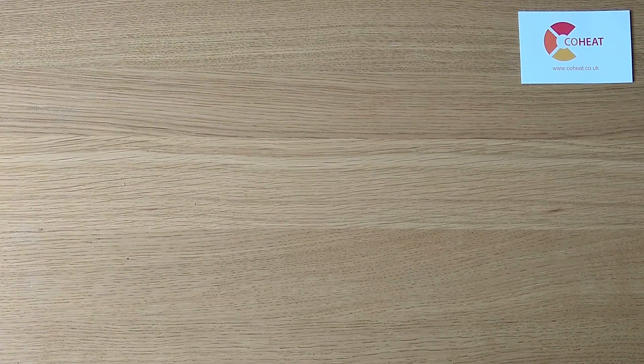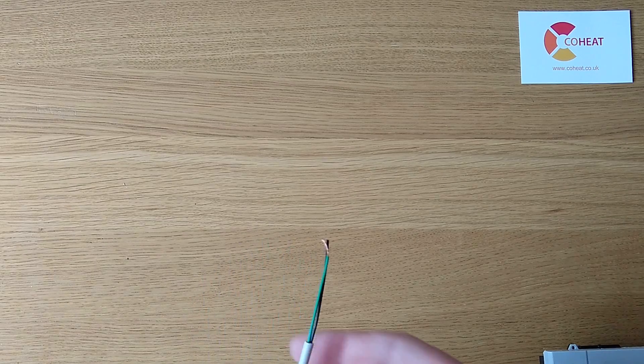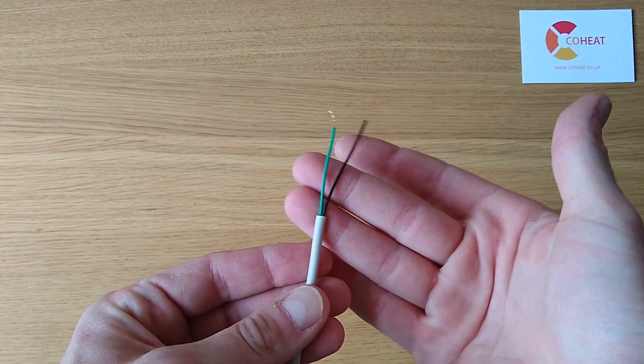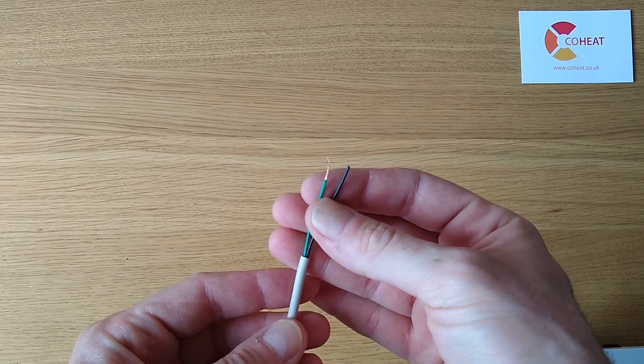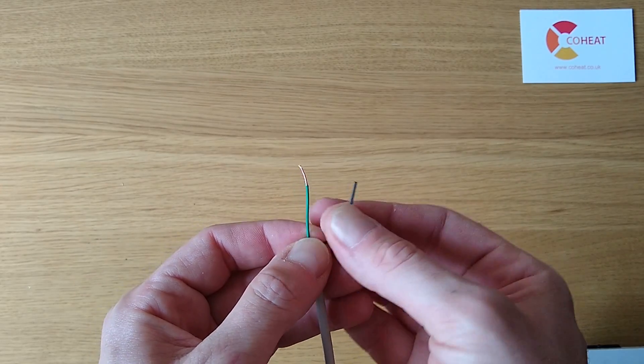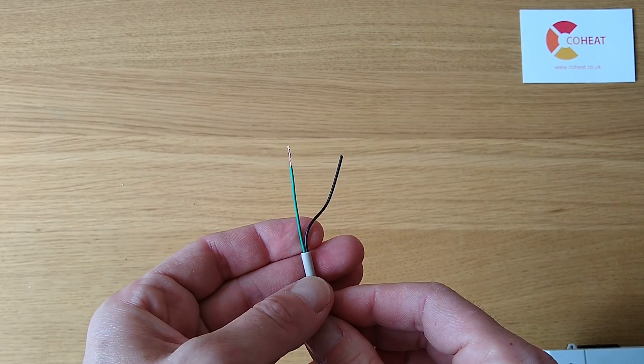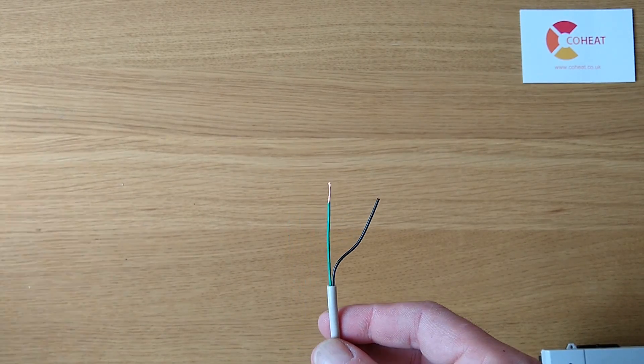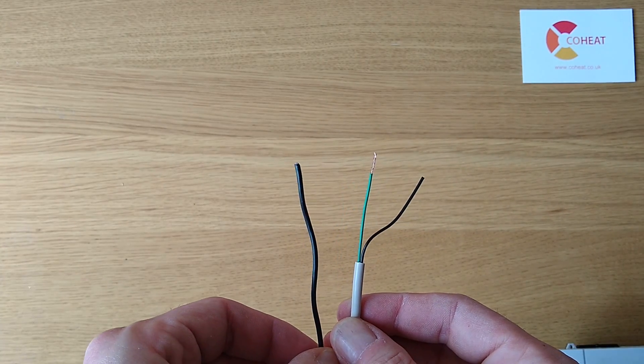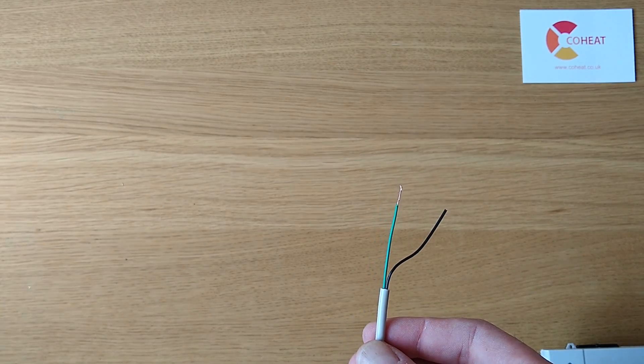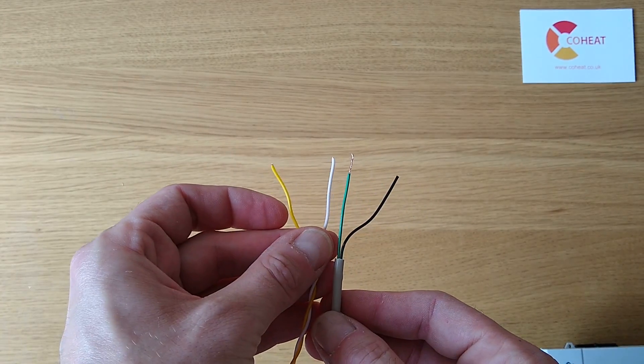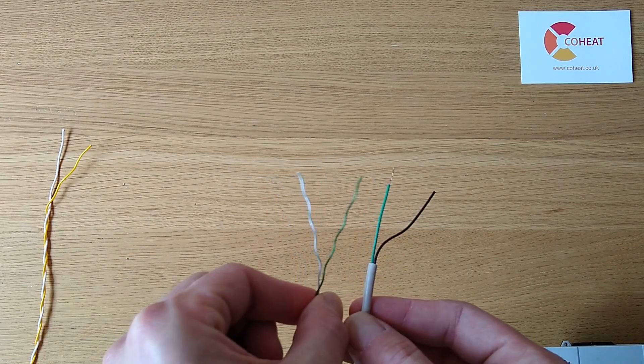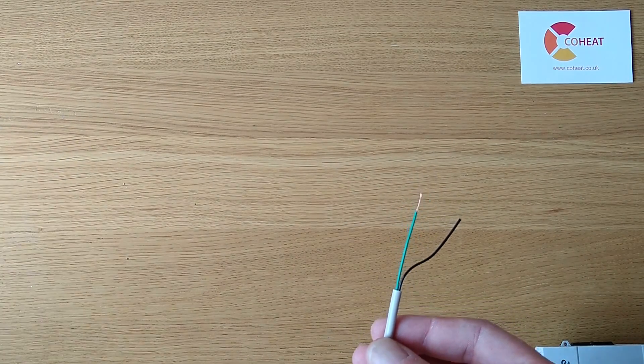Some heat meters, particularly the cheap ones, or the compact meters designed for use in the heat interface unit, come with pre-molded cable that cannot be replaced. And this often has really thin, stranded cable, which you're expected to join to some Belden 8760 style cable, or perhaps some EIB KNX style cable, or some Cat5. How do we do this?